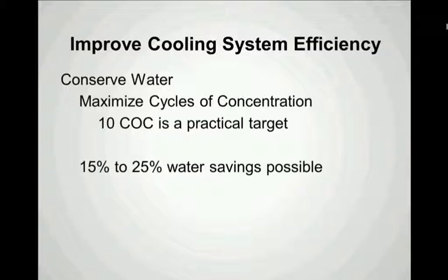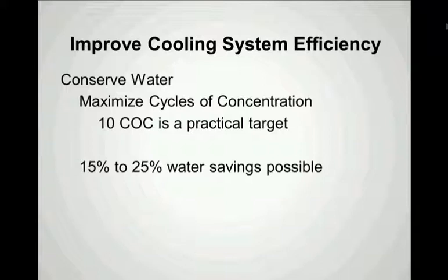First, in order for a system to operate efficiently with regard to water consumption, we need to focus on maximizing the cycles of concentration. A practical target for many cooling water systems is 10 cycles of concentration. One way to estimate your limit is through the cycle of concentration estimator tool, which calculates that based on your makeup water quality. If the result is less than 10 cycles, you can ask whether there are alternative methods for pre-treating the makeup water to allow higher cycles of concentration.